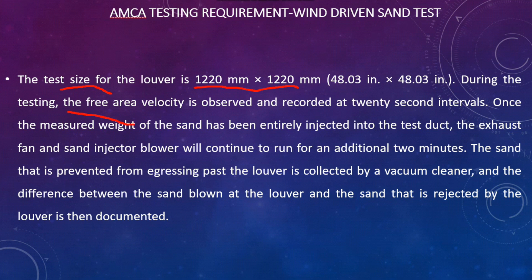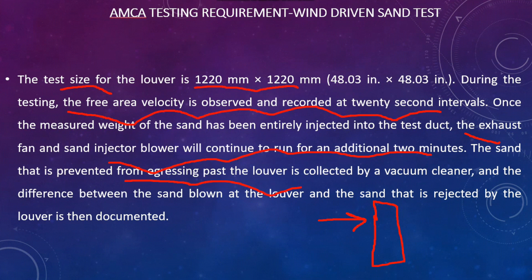During the testing, the free area velocity is observed and recorded at every 20-second interval. The test blows a measured amount of sand — for example, 5 grams — onto the louver using an exhaust fan and sand-injected blower, running continuously for 2 minutes. The sand prevented from passing through the louver is collected by a vacuum cleaner. The difference between the sand injected and the sand that passed through is measured, and based on that the sand rejection performance is determined. There are four grades: Class A is 90–100% effective, Class B is 80–89.9%, Class C is 70–79.9%, and anything below 70% falls into Class D.